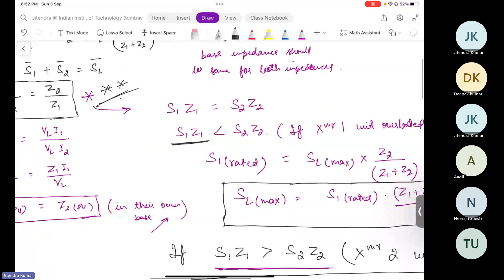Sir, if this condition is satisfied, then we just have to add the kVA ratings, and we can say the maximum load we can connect is this much amount. If this ratio is satisfied, in such a case, none of your transformers will get overloaded. That's why I broke it into two cases where S1Z1 is less than S2Z2, or S1Z1 is greater than S2Z2. Only two things can happen, right? So if one is less than the other, it means you are not providing appropriately according to the ratio, so one of the transformers is going to be overloaded.